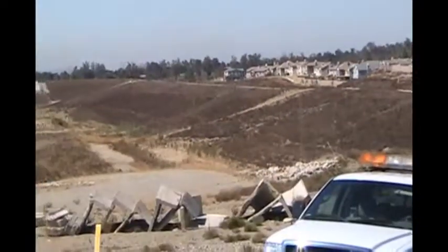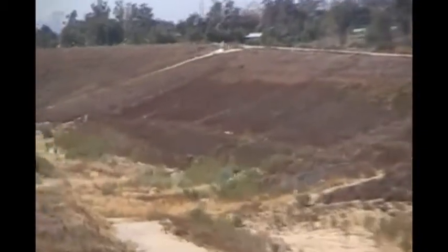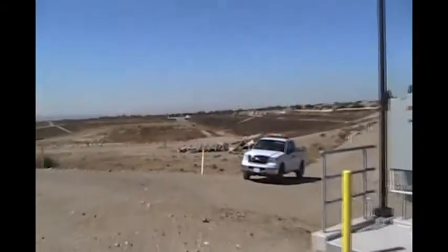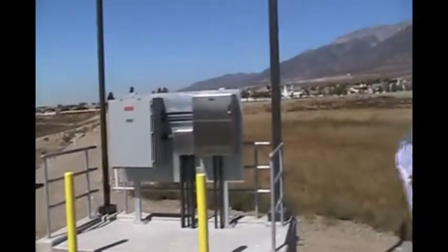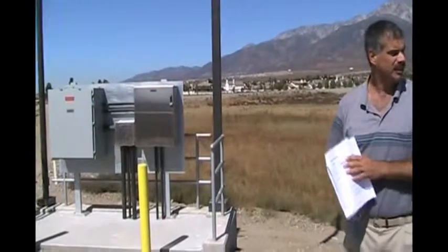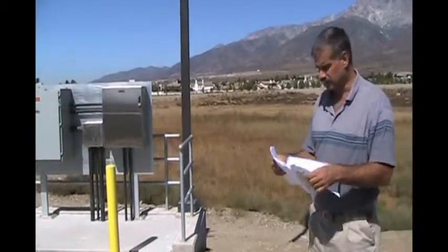This particular site is set up from a solar cell. We checked the UPS on this, and it ran from Friday to Monday without any trouble at all, with the solar panel disconnected. In communications back to the SCADA, you can program here at this site. It can also be programmed from the SCADA. Once changes are made, they are recorded at both locations, so that if somebody makes a change at the SCADA while you're here, you'll see it, and vice versa. If you make changes, they'll see it on the SCADA.